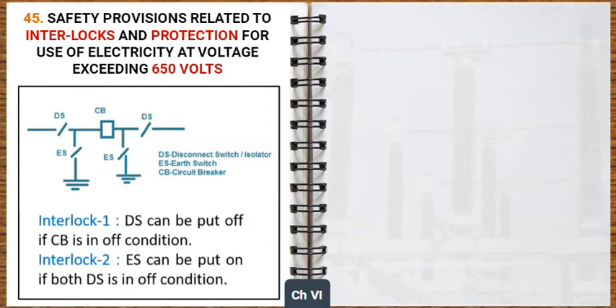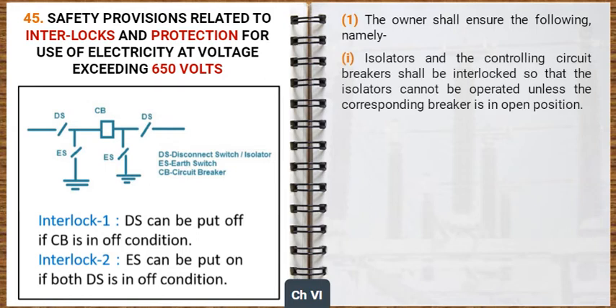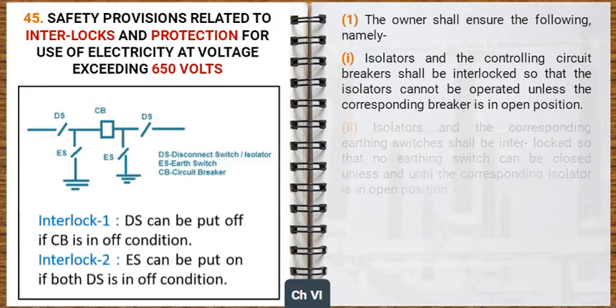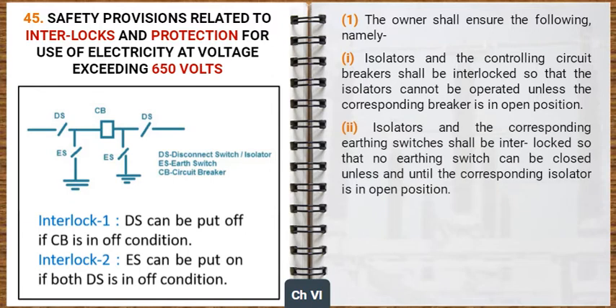exceeding 650 volts. The owner shall ensure the following, namely, isolators and the controlling circuit breakers shall be interlocked so that the isolators cannot be operated unless the corresponding breaker is in open position. Isolators and the corresponding earthing switches shall be interlocked so that no earthing switch can be closed unless and until the corresponding isolator is in open position.